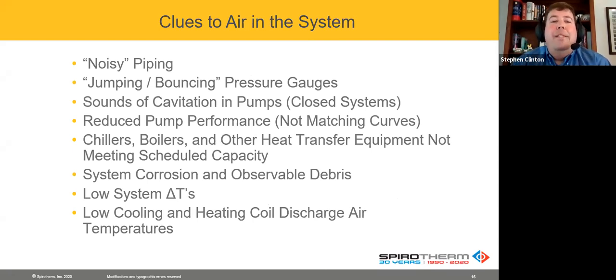How do I know I have air in my system? Well, think about it. If you walk through a mechanical room, not even a mechanical room, walk through a school or a hospital or a research lab or somewhere. If you walk down a hallway or in a room and you hear a flow noise above you in the piping system, that's not water, that's air. Because unless water is superheated or at very high velocity and pressure, it's not going to make noise. So that's air that you're hearing. The other thing is, if you walk into a typical mechanical room and you see pressure gauges, they're fluttering, they're jittery, they're bouncing. That can't happen with a non-compressible fluid like water. But if air is having micro pressure changes, that's why you get that.